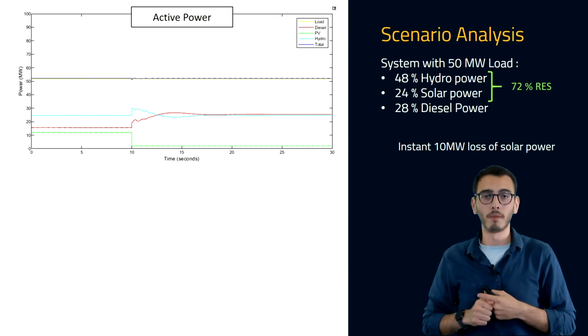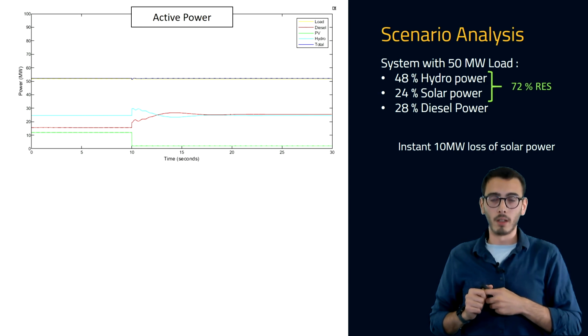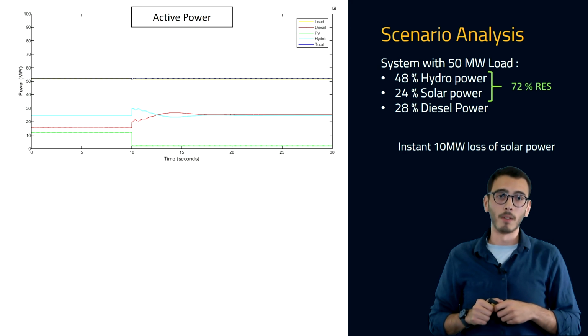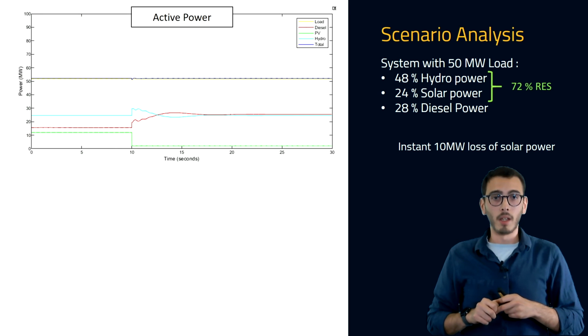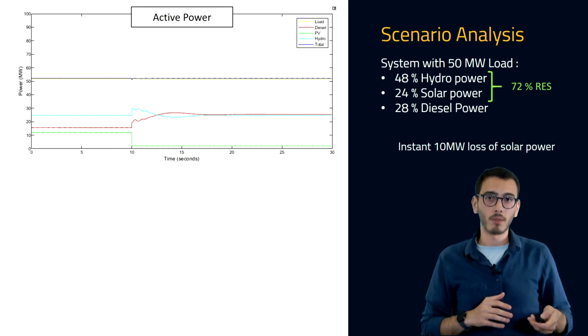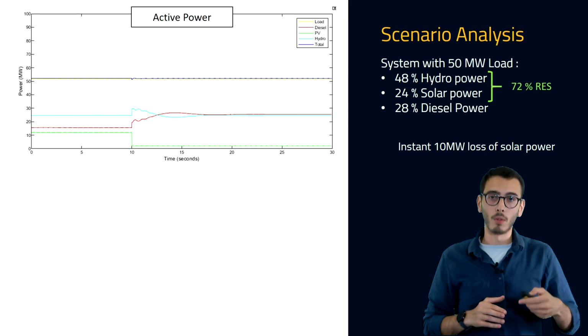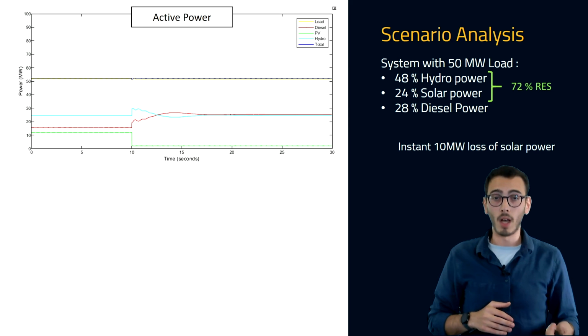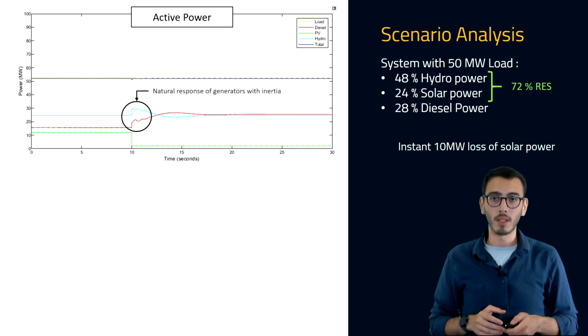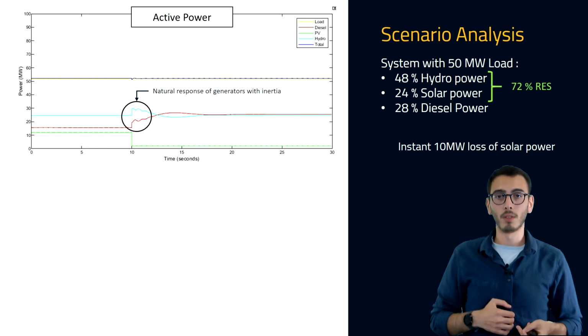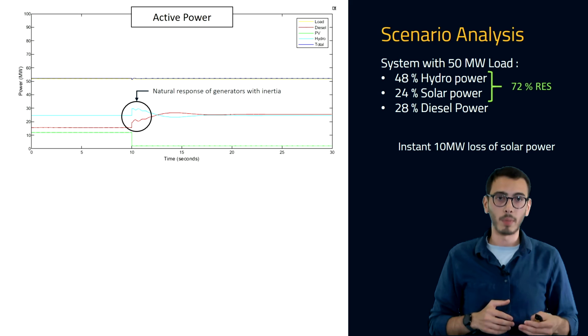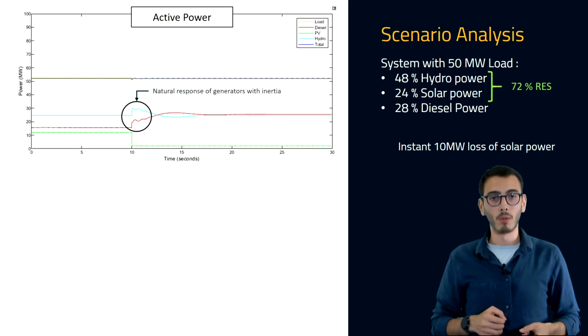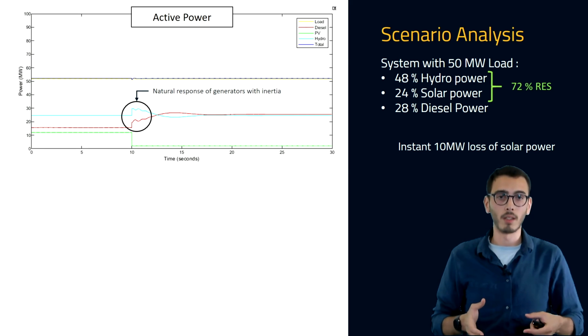So as you can see in the graph right above me, the green line indicates the solar energy. At an instant time equal 10 seconds, we have a drop from 12 megawatt to 2 megawatt. So we can see how the system reacts to that. First of all, for the blue and the red, which demonstrate the hydro and the diesel electricity, you can see at first the natural response of generators due to inertia. So as I explained, inertia is quick to inject power because of the stored energy inside these rotating elements.